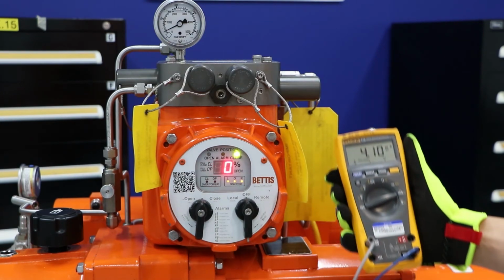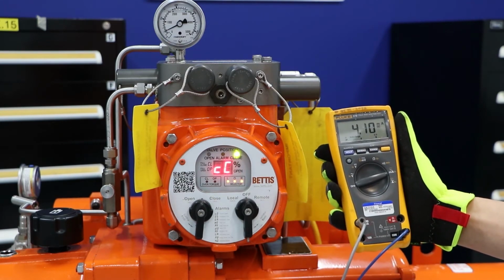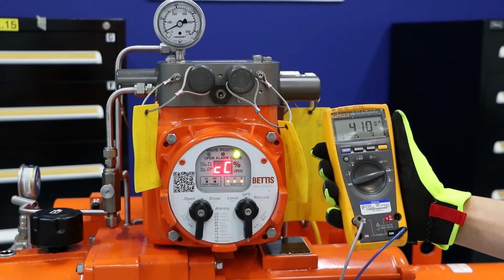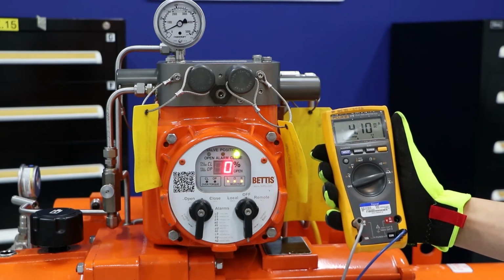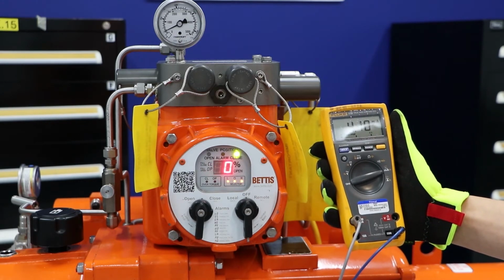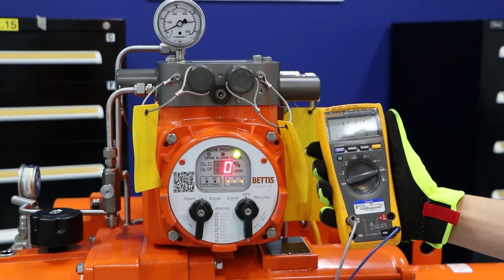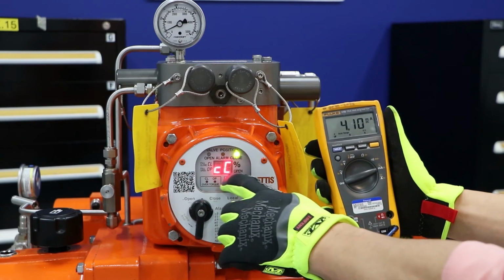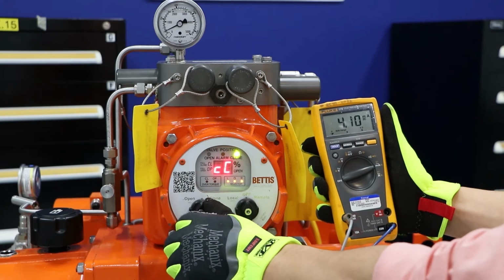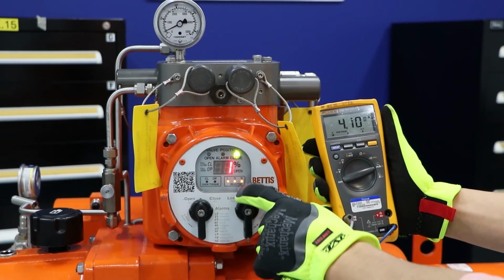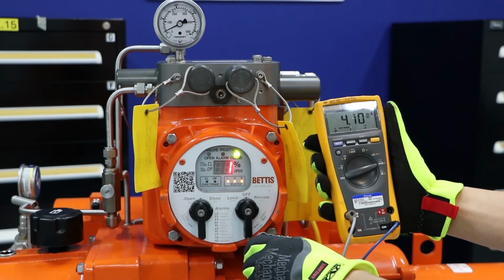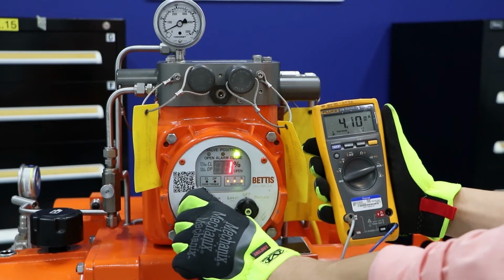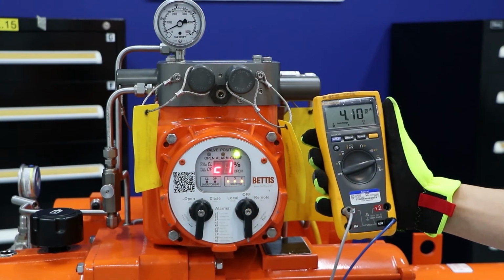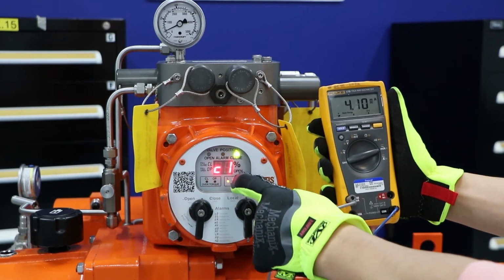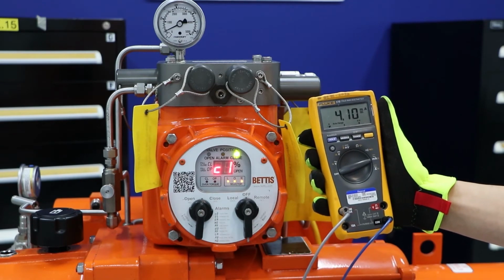Now take a look at your multimeter. On our multimeter, it reads 4.1 milliamps. We want to get to 4 milliamps. So we have to decrease the value. So if this is the case, we want CC to read 1. So we'll hit no. And now CC is 1. Once we do that, we'll hit yes. And now you see C1. So we're ready to calibrate this.